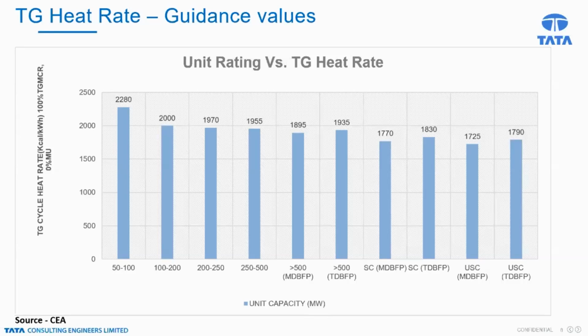These are the guidance values published by CEA for various unit ratings. What is the turbine cycle heat rate at the design condition, 100% TGMCR? That means 100% power output by the turbine at the generator terminal and 0% makeup. These are all guidance values, and as a consultant, we used to specify that the suppliers should at least match these or provide better heat rates than these. That is the expectation. So this gives a broad guidance value for the turbine cycle heat rate for various capacities.